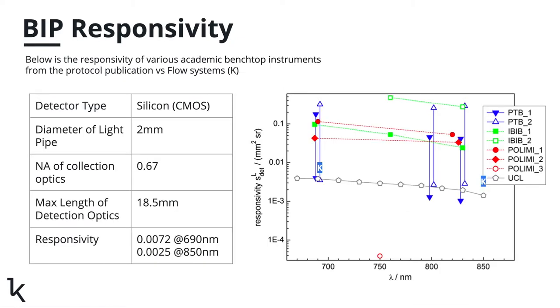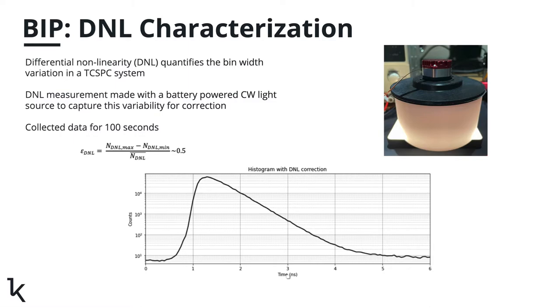When we compare the performance of our modular system versus other reported TD-NIRS systems, as you can see from the K marks on this chart, we perform comparably to the previously reported systems. It is important to note that our detector is a silicon-based detector made using a commercially available CMOS process. As such, it has lower intrinsic responsivity than the PMT-based systems referenced in this chart. Additionally, we are not using any fibers for our collection system and use a short light pipe with two millimeter diameter and numerical aperture of around 0.67.